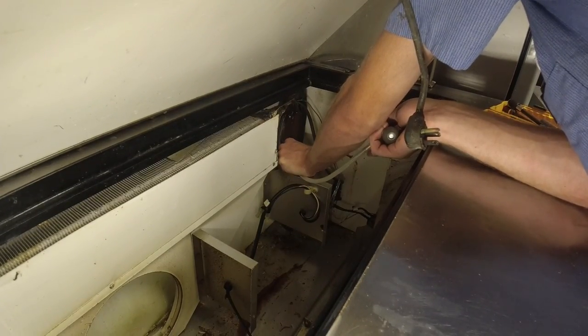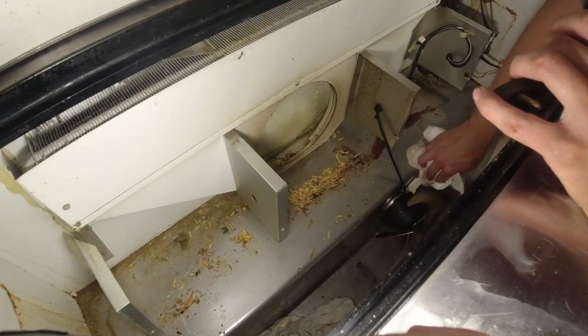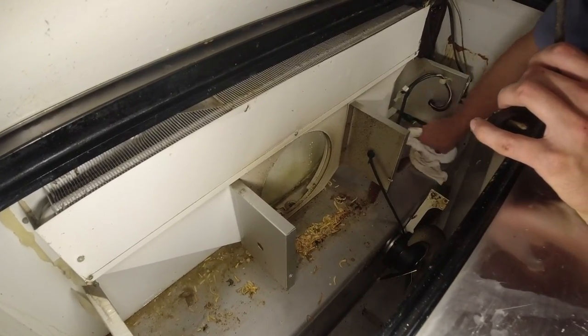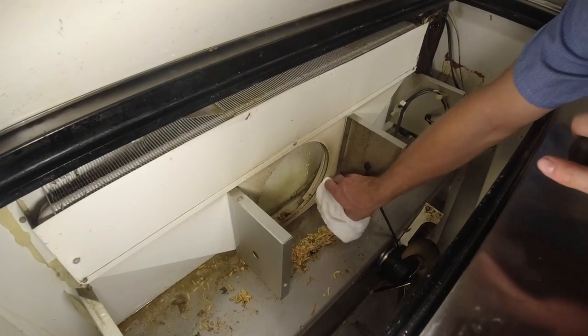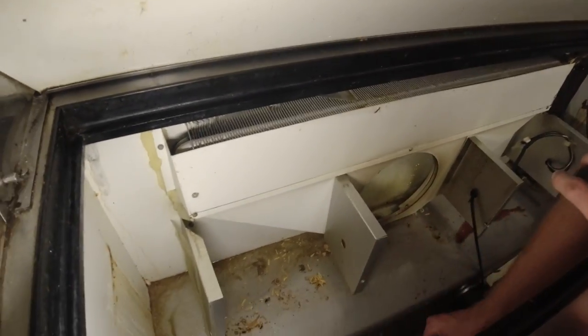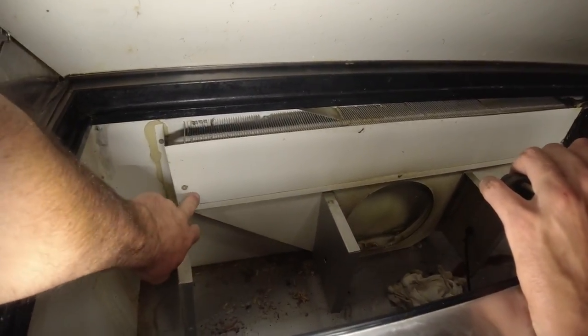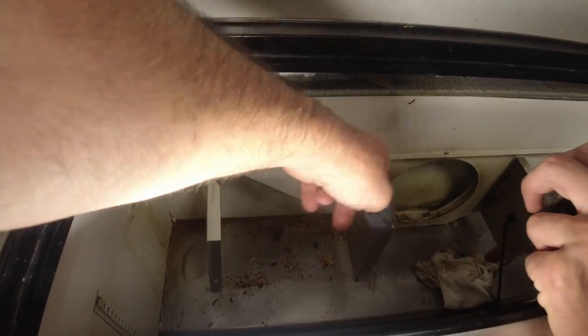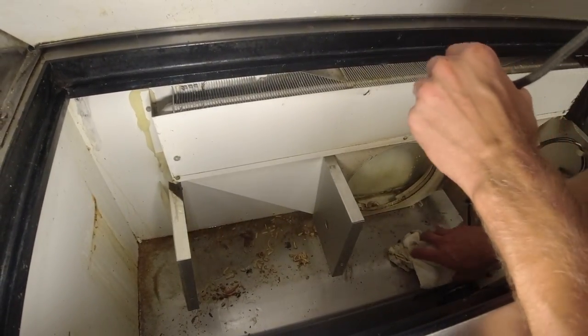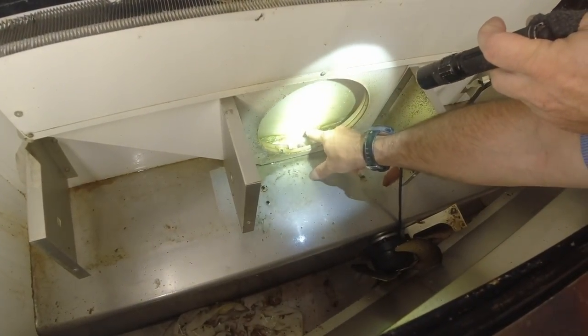Sometimes we're just a bunch of lonely cooks cleaning up the prep line. The most important part is going to be inside the actual pan area - we could have some seals leaking through. Do you feel any water on the back side? It's kind of damp. This whole piece comes off with silicone squeezed behind it - it could be leaking down that silicone going around it and falling down. There's a little bit of a gap down here.